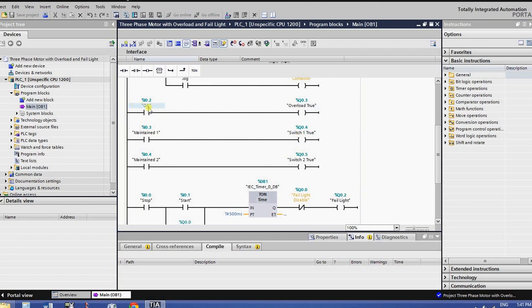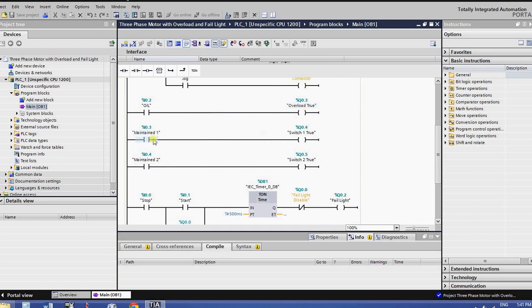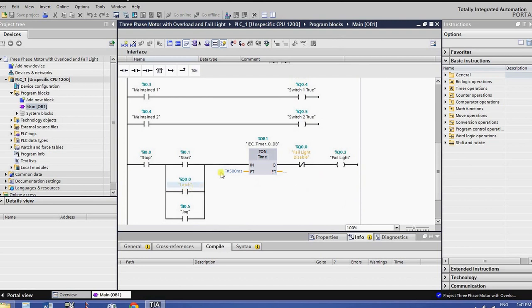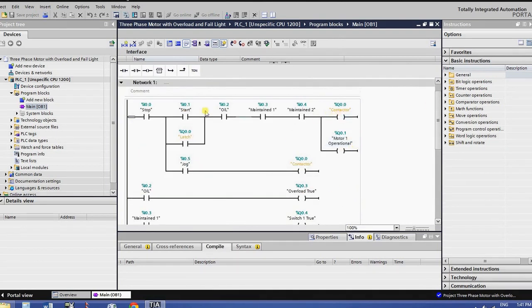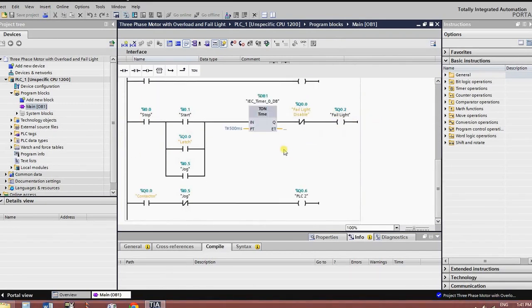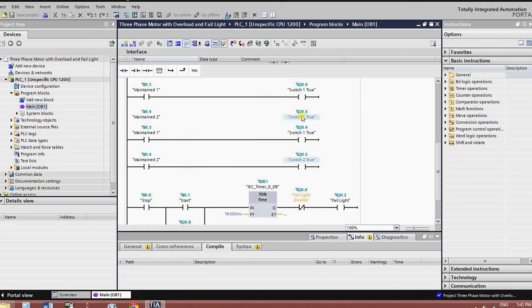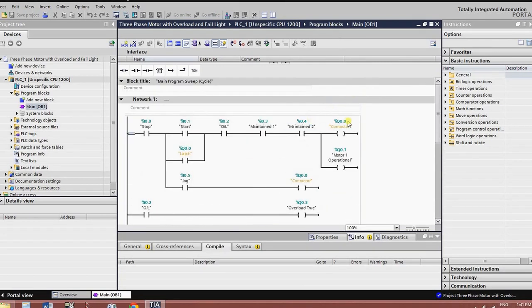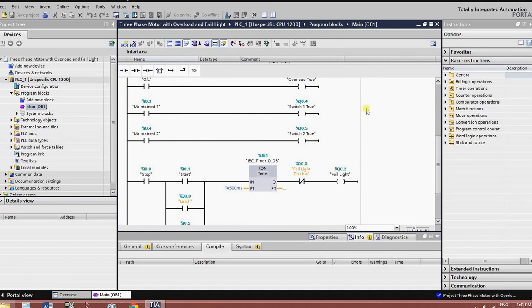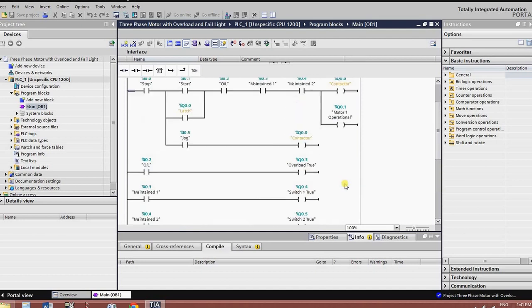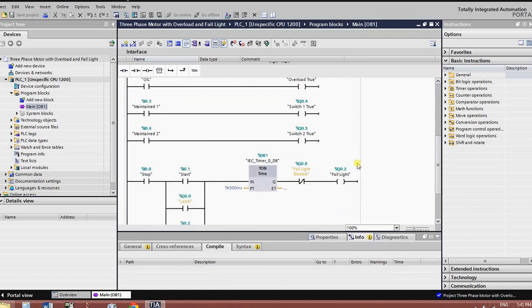So if your overload is true, or your overload is working, the overload working light will come on. If your maintain switch at the bottom of your panel is on, the light will come on and tell you that. I've also hooked up a fail safe light, so in the event that you do all this and your contactor does not work, when you push the start button, half a second after you push it, if the contactor up here has not come on, then the power will go through this timer, through this normally closed contact, and go to the failure light, which is essentially just another light that'll be somewhere in the panel, and it'll say motor 1 not working.